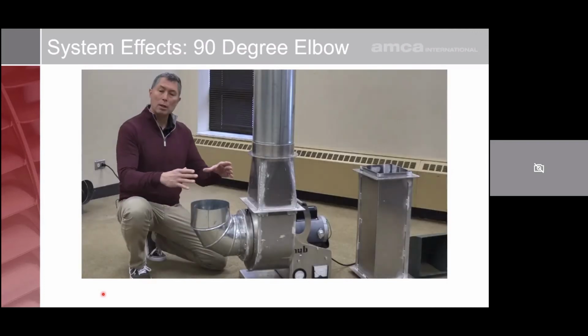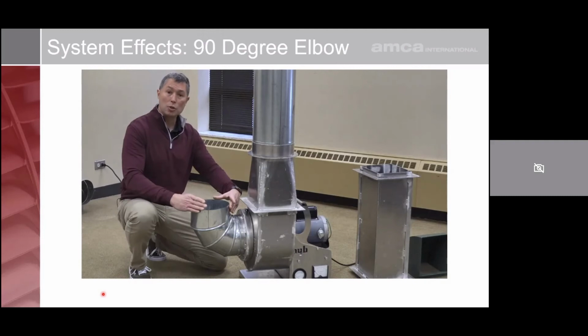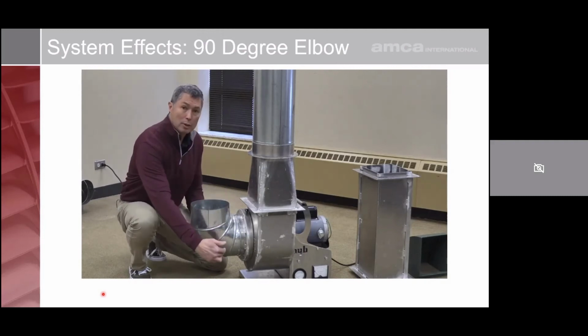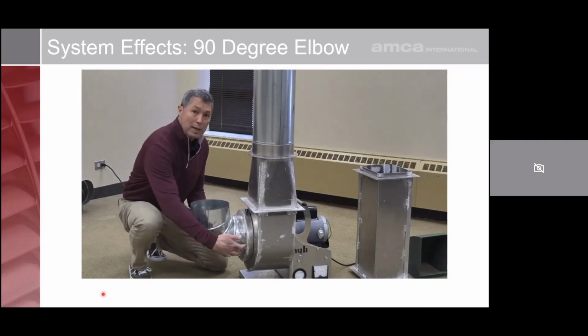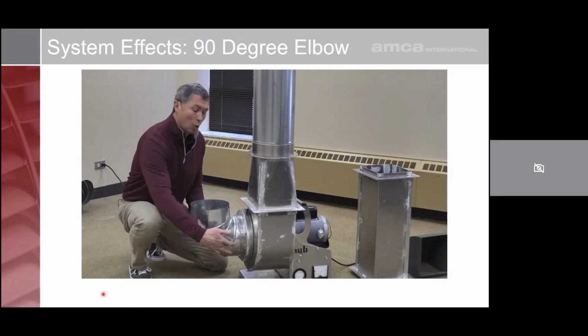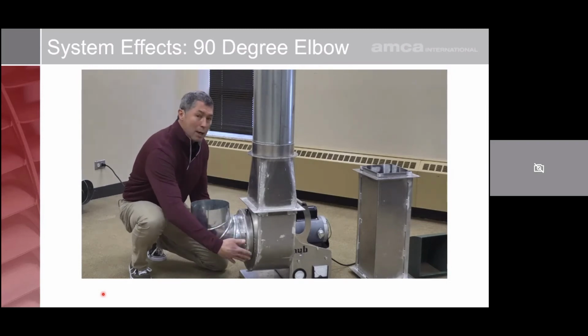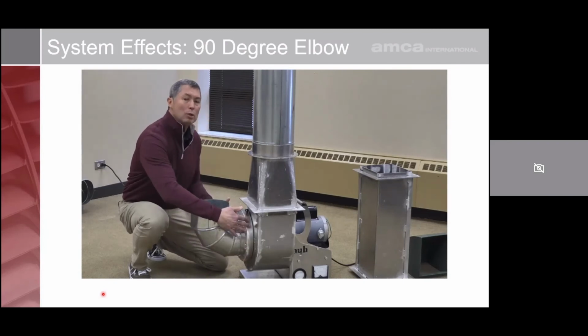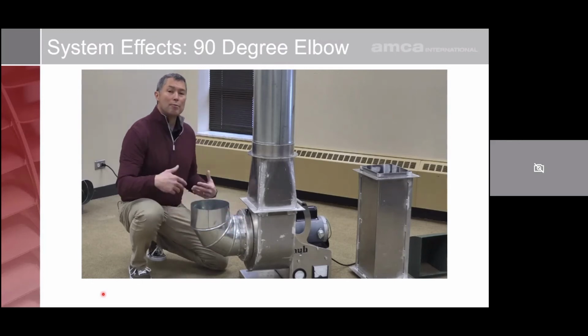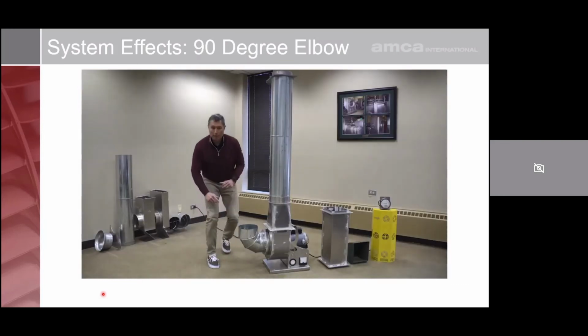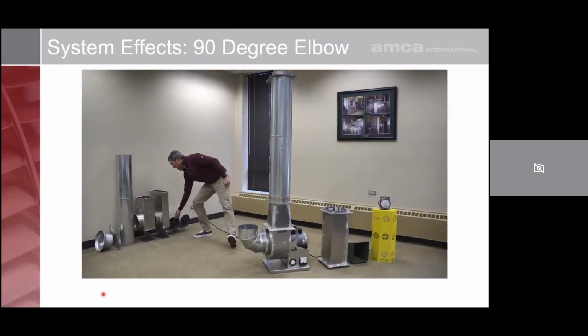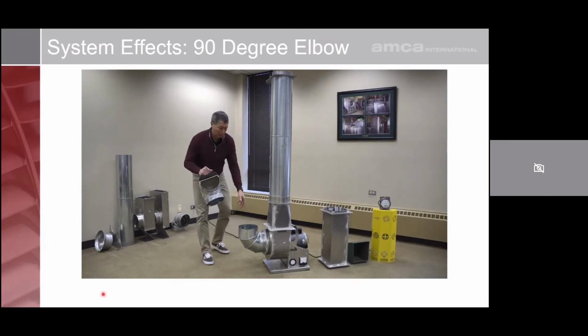What's happening is air has mass, and when anything has mass, it wants to go in a straight line. So the air enters this duct uniformly, it wants to go straight down to the bottom, and then it has to bend 90 degrees into the fan. So basically we're loading the bottom half of the fan wheel as it's rotating, but the top half of the fan wheel doesn't get any air, so we're not fully utilizing the mechanical aspects of this fan.